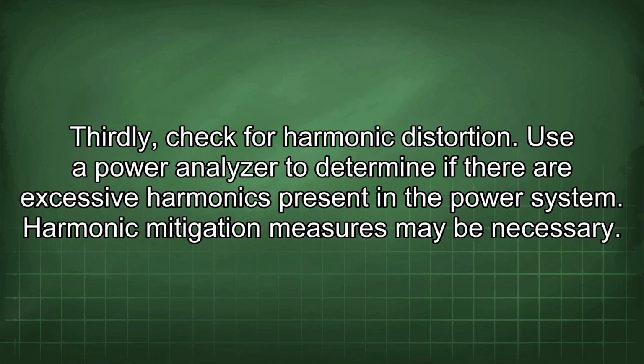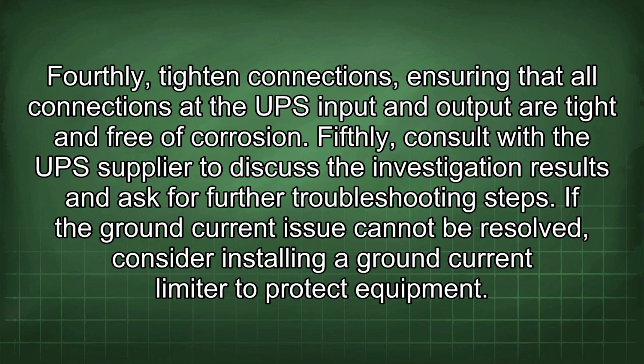Thirdly, check for harmonic distortion. Use a power analyzer to determine if there are excessive harmonics present in the power system. Harmonic mitigation measures may be necessary. Fourthly, tighten connections, ensuring that all connections at the UPS input and output are tight and free of corrosion. Fifthly, consult with the UPS supplier to discuss the investigation results and ask for further troubleshooting steps. If the ground current issue cannot be resolved, consider installing a ground current limiter to protect equipment.